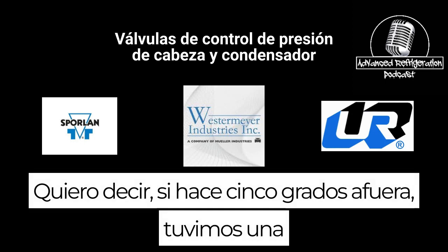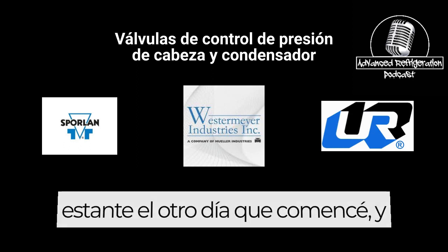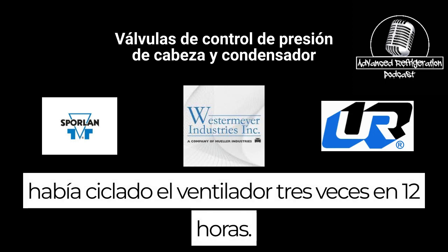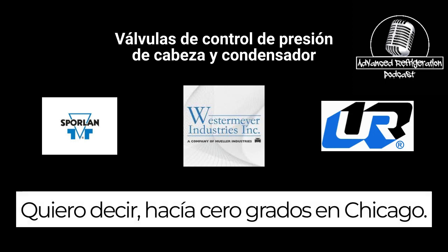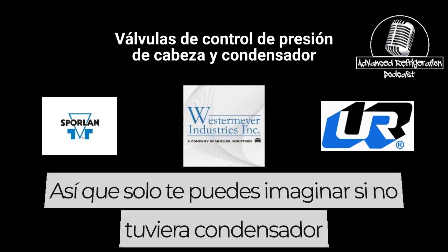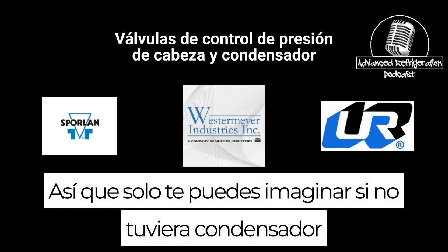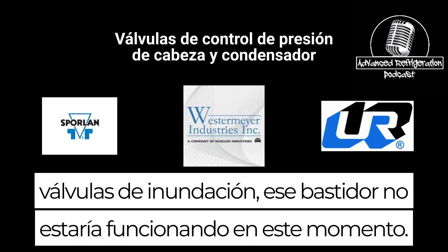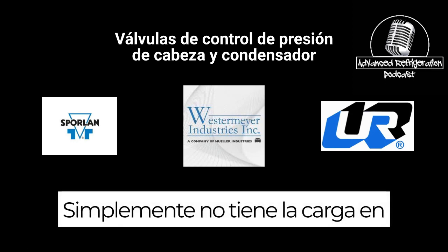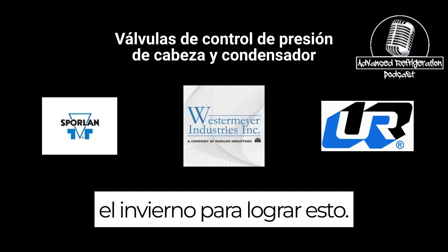I mean, if it's 5 degrees outside, we had a rack the other day that I started up and it had cycled the fan 3 times in 12 hours. I mean, it was 0 degrees in Chicago. So you can only imagine, if it didn't have condenser flooding valves, that rack wouldn't be running right now. It just doesn't have the load in the wintertime in order to accomplish this.